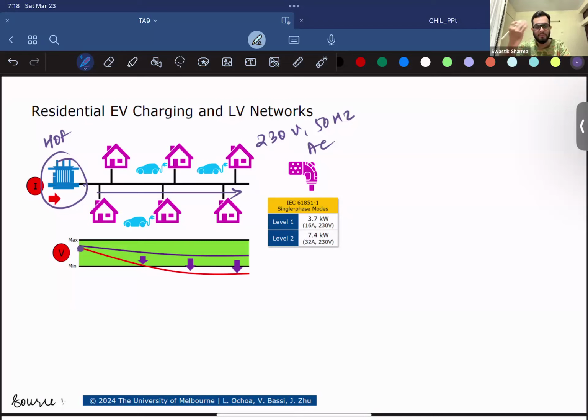Why is that? The amount of current being imported from your distribution transformer will increase as soon as you charge your EVs. Since this current is increasing, the losses are also increasing in the system. If these losses increase, the voltage at the last terminal of the feeder falls. If you're at the head of the feeder, connected directly to the distribution transformer, you are in a win-win situation because you won't experience that high loss.